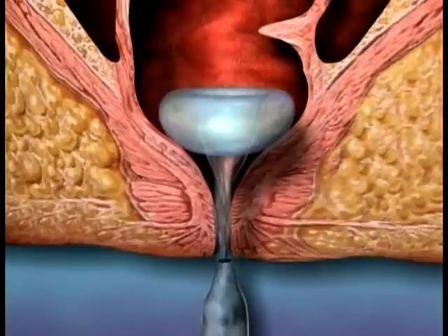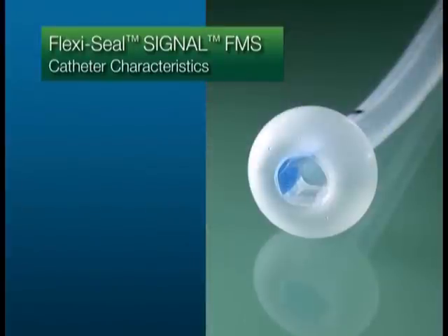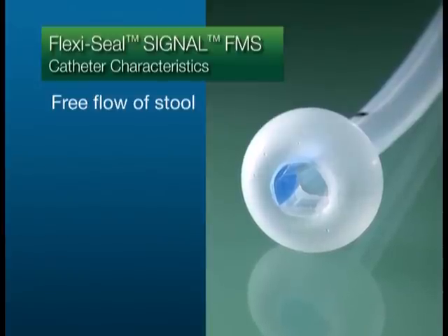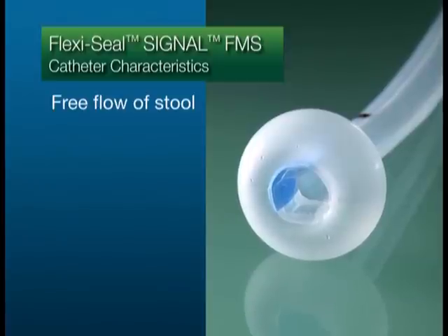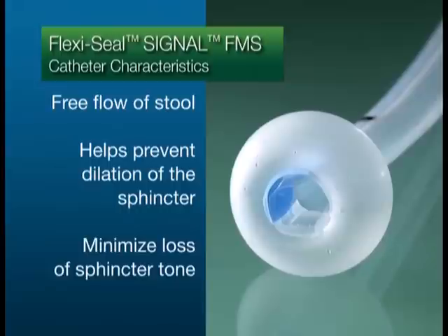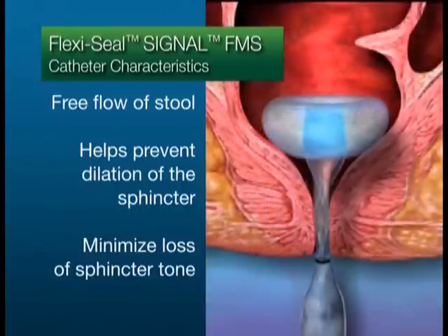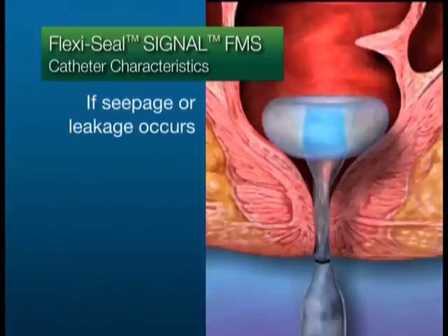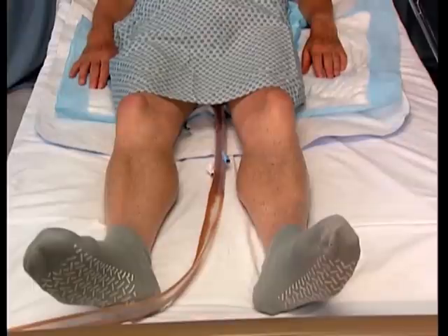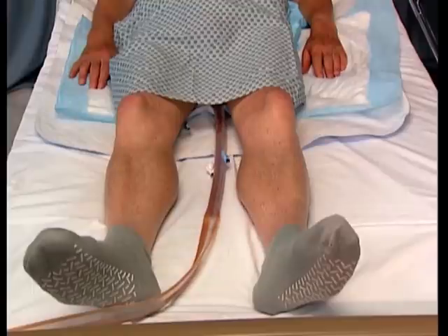You should observe changes in the location of the position indicator line as a means to determine movement of the retention balloon in the patient's rectum. This may indicate the need for the balloon or device to be repositioned. The catheter's large 22 millimeter diameter is designed for free flow of stool and is capable of collapsing to a very small 8 millimeter diameter. This ability of the soft flexible silicone catheter to collapse to an 8 millimeter diameter helps to prevent prolonged dilation of the sphincter, helping minimize the risk of loss of sphincter tone. A small amount of seepage is therefore expected. If more than a small amount of leakage occurs, this is likely a sign that the retention balloon should be repositioned. Patients with very weak sphincter muscles may not be able to hold the device in place and may experience increased leakage of stool.